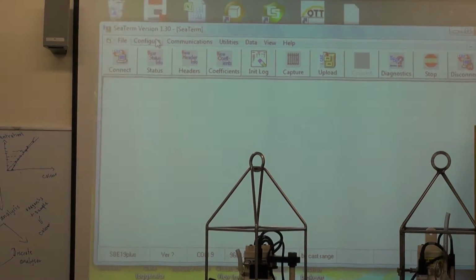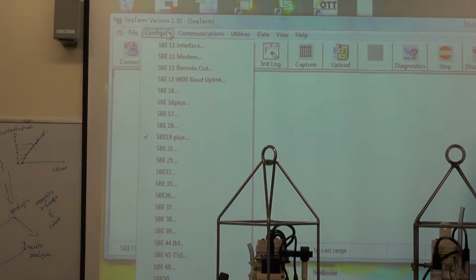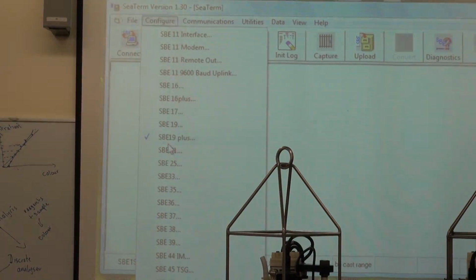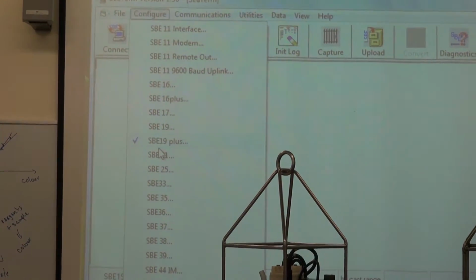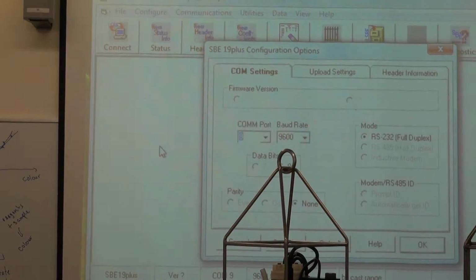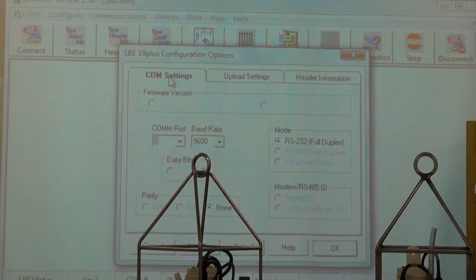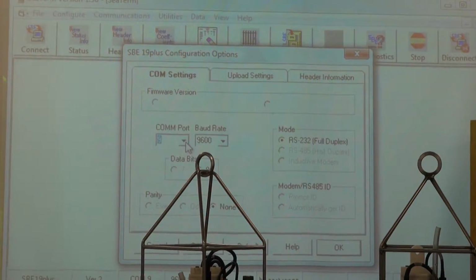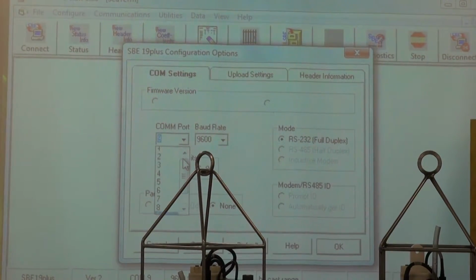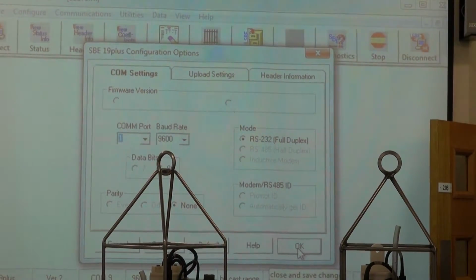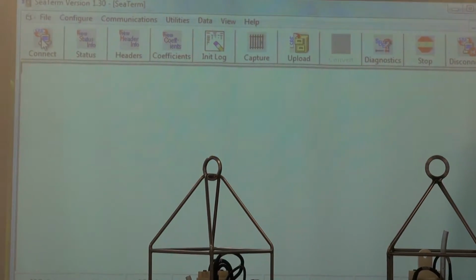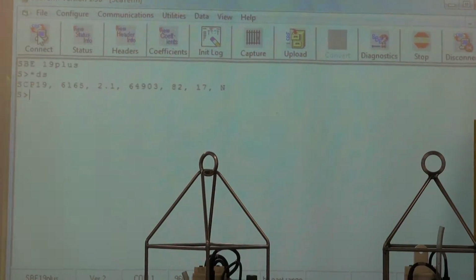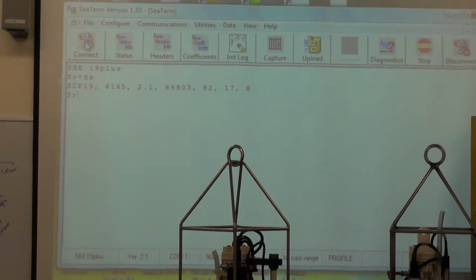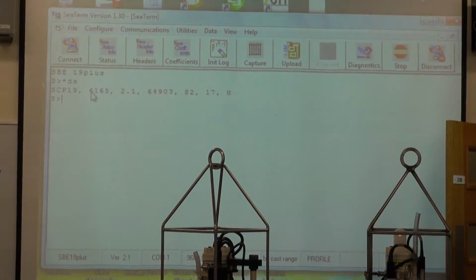Now if we go to configure, under the CTD software menus, select our instrument type, which for both of these instruments is a SBE 19+. And we can see here our first tab is COM settings. Got a pull down menu there. Change the port it's looking for to match the port that's assigned to that adapter. Click OK. Now we should be able to connect to the instrument. So it's giving us a few readouts here. You can see in the top line here's the serial number of the instrument, 6165, with the new CTD.